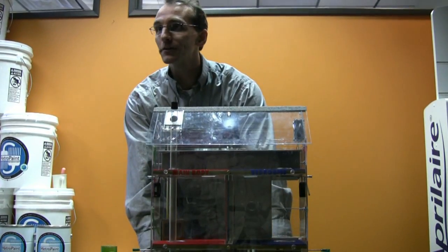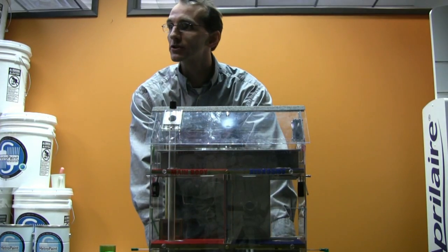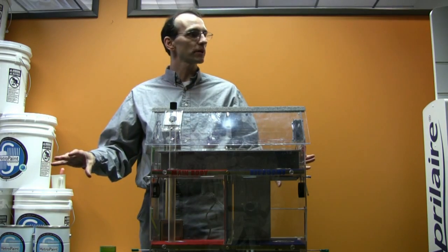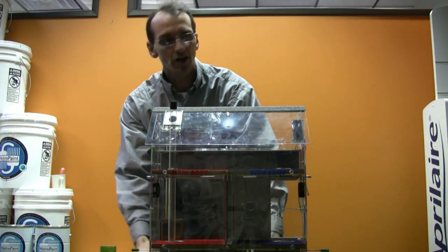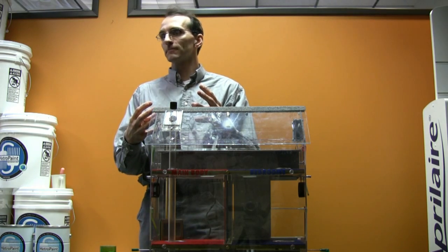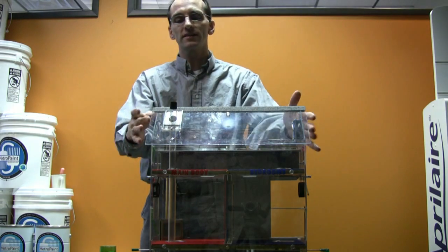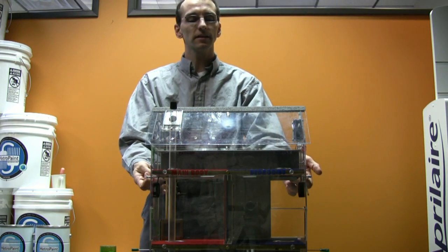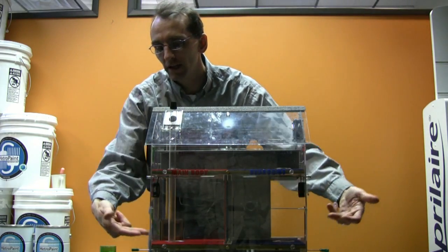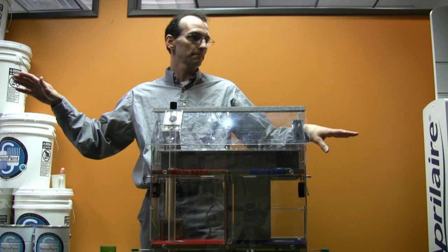And that means at the bottom of the house, you pretty much always, all year long, have a negatively pressured crawl space or basement or right above the slab. It is always negatively pressured, which means this part of the house is always sucking air in from whatever's around it. Okay? And up here, just inside this roof plane, it's always positive. Or if this is a ventilated attic, just under this insulated roof, it's always positive. And somewhere in the middle of the house, you have a neutral pressure plane. It's not positive or negative there.